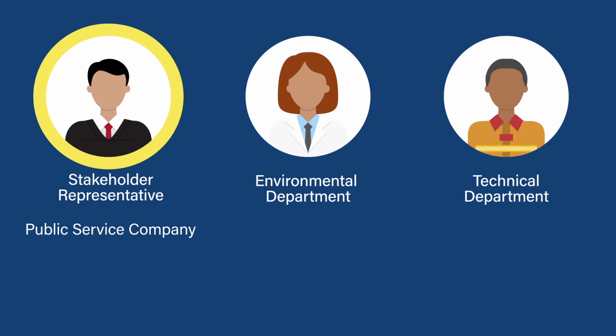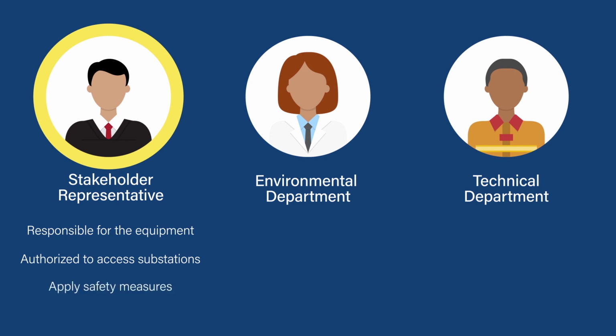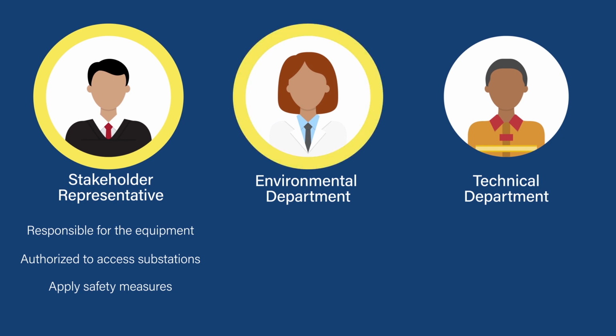Since sampling transformers can be dangerous, it is necessary to follow health and safety procedures throughout sampling. Therefore, the stakeholder representative should be an experienced engineer responsible for the equipment and be authorized to enter a transformation substation, disconnect the equipment, or work with live transformers, if necessary, and verify compliance with the safety procedure during sampling.